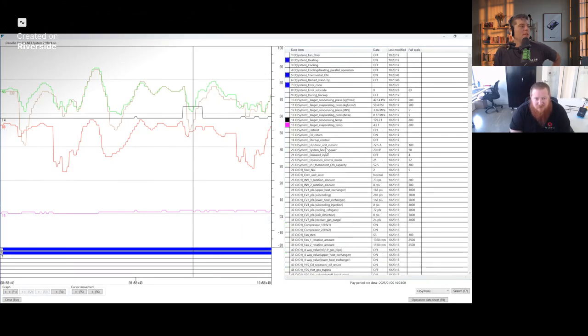But in heating mode, the unit is only controlling compressor speeds off of target condensing temp. So again, if my compressor is acting erratic, what does my target condensing temp look like? What does my condensing temp look like? If I'm in cooling mode or in parallel operation, I might plot both to see which one it's actually trying to drive to. And it'll hit that and stop modulating compressors. If it overshoots it, it'll slow the compressor down. If it's still under it, it's going to ramp the compressor up.